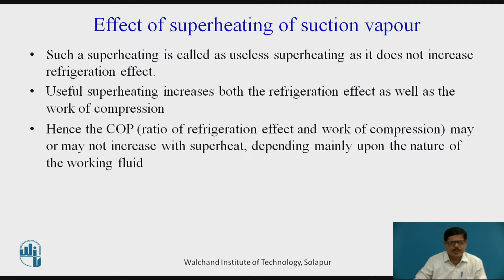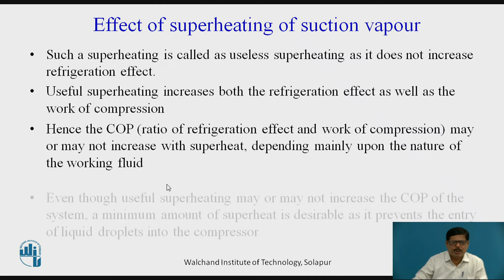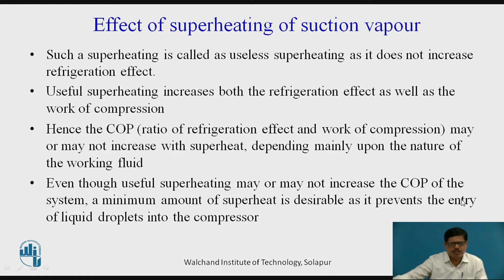Therefore, the COP — which is the ratio of refrigerating effect to work of compression — may increase, decrease, or remain the same with superheat, depending upon the nature of the refrigerant or working fluid. Whether COP increases or decreases with superheat depends on the type of refrigerant. But even though superheating may or may not increase COP, a minimum amount of superheat is always desirable because it prevents the entry of liquid droplets into the compressor. For a reciprocating compressor, liquid refrigerant must not enter. Therefore, superheating always prevents liquid droplets from entering the compressor and ensures complete vaporization of the liquid.